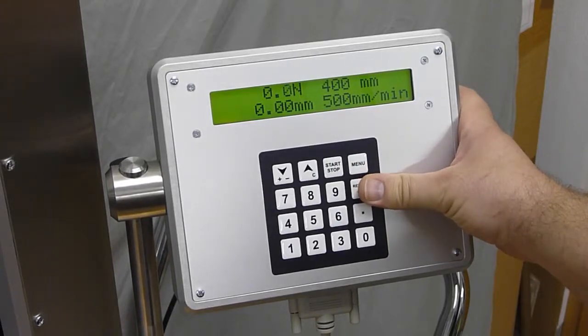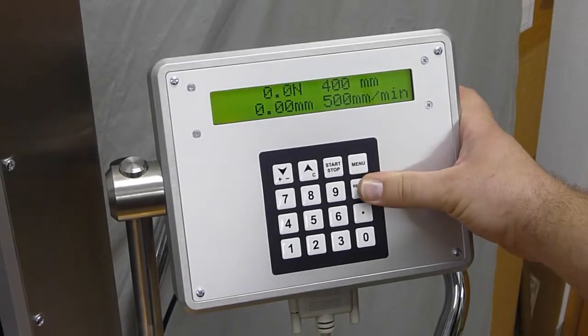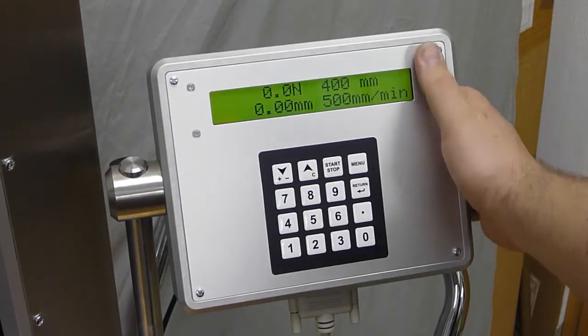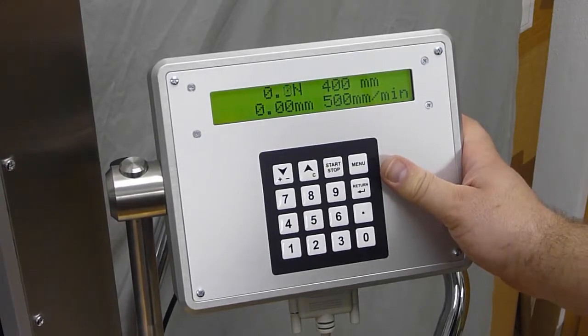In this case, when in 20ms force falls down over 100N, the test is broken and the machine finds out something happened with the sample.